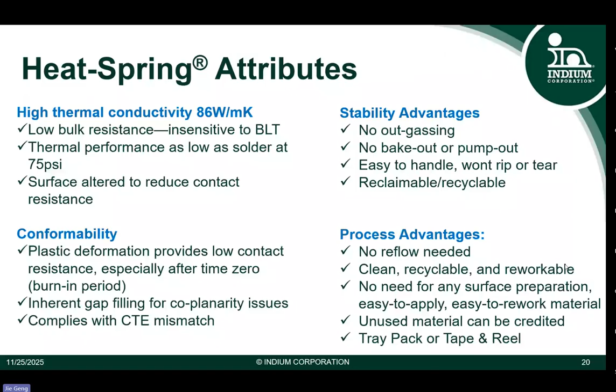The major application for the heat spring is TIM 1.5, the bare die to heatsink. The most advantageous part is the heat spring can be used for immersion cooling, because there's nearly no reaction between indium and most immersion cooling liquids. We did a test of the compatibility of different types of TIMs with the immersion fluid. In the picture at the bottom you can see after a couple of months, the indium metal is the only TIM that doesn't react with the fluid.